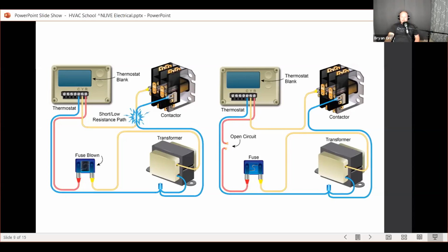It's fine to use a voltage rating on a fuse, on a fusible link, that is higher than the rating of the old one. So it's totally fine to use a higher rating on the voltage, not on the current. So you've got to match the current exactly, but it's fine to use a higher voltage rating, because that's just saying that is the voltage at which, when you go over that, it can actually bridge the fuse itself. So a higher voltage rating on a fuse is a better quality. It's not actually there to protect the unit for that higher voltage.